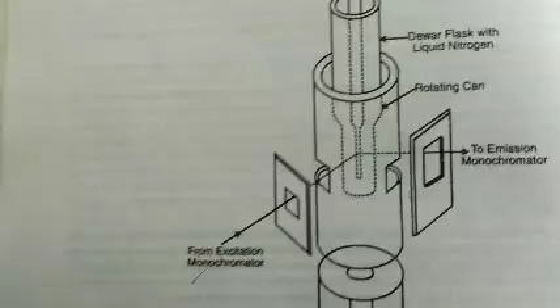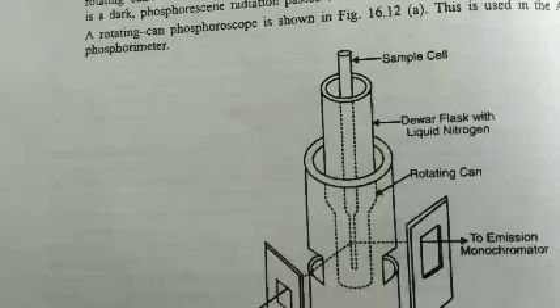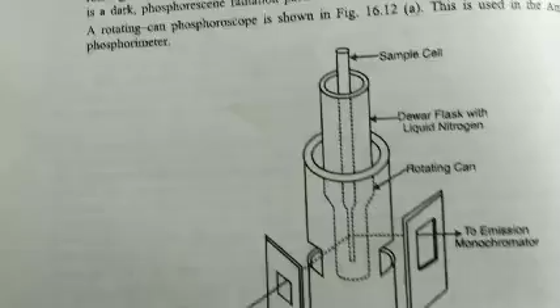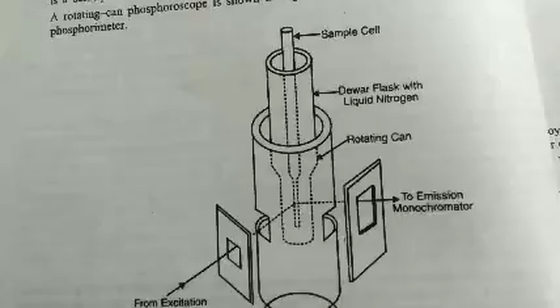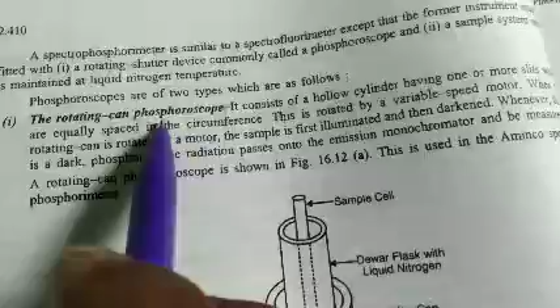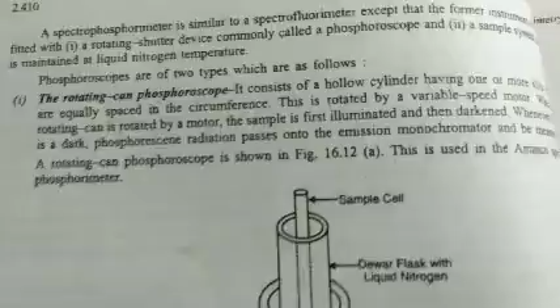We have already seen the instrumentation of fluorimetry. Like in fluorimetry, the phosphorimetry instrument mainly consists of a light source, a filter or monochromator, and a detector. There are two main types of phosphorimeter: the rotating can phosphorimeter, and second, the rotating disc phosphoroscope.